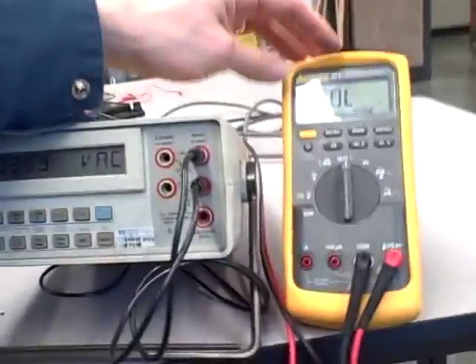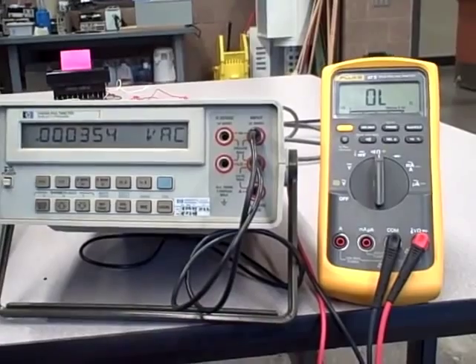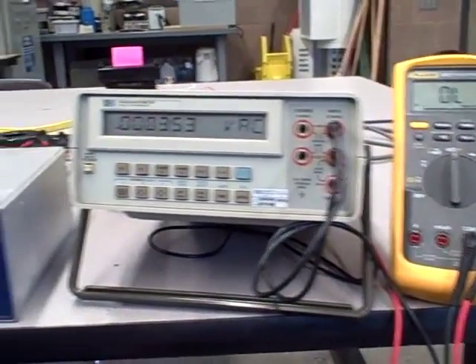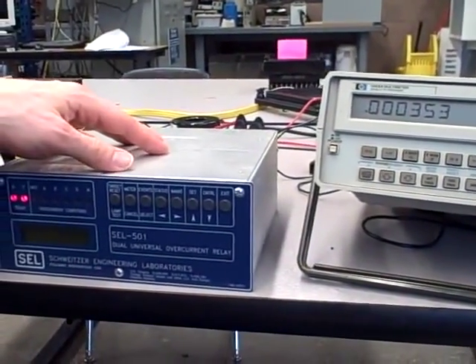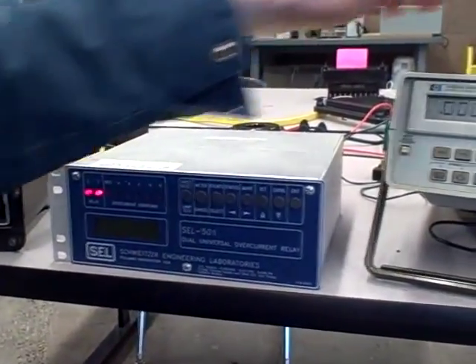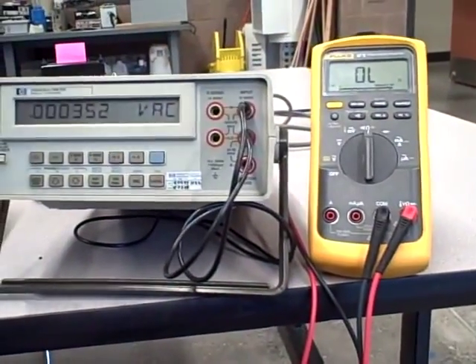We also have a Fluke multimeter attached measuring ohms to measure the continuity of the trip contact on the back of the Schweitzer relay. So when this encounters a trip event, we'll close that contact. We'll signify that by the Fluke meter beeping at us.